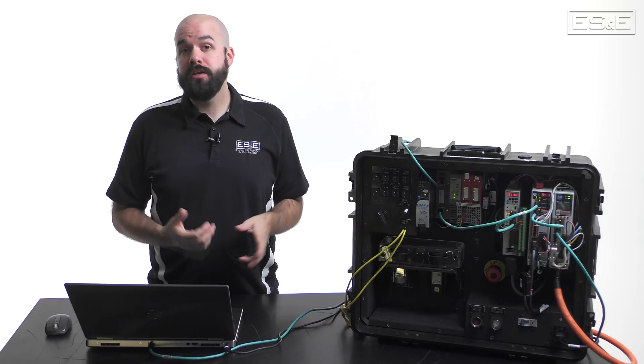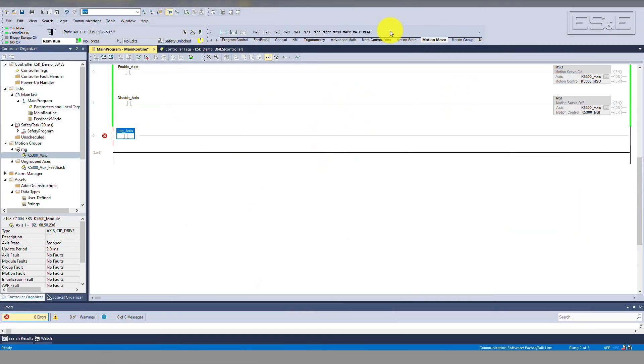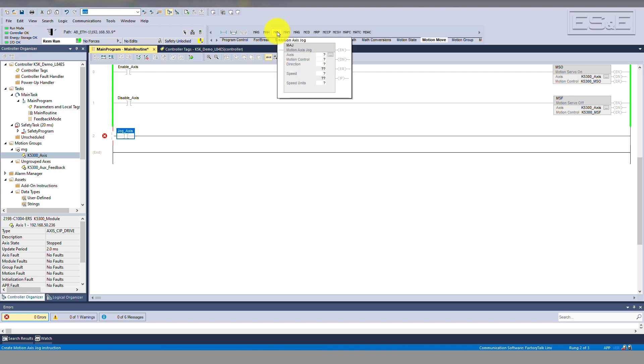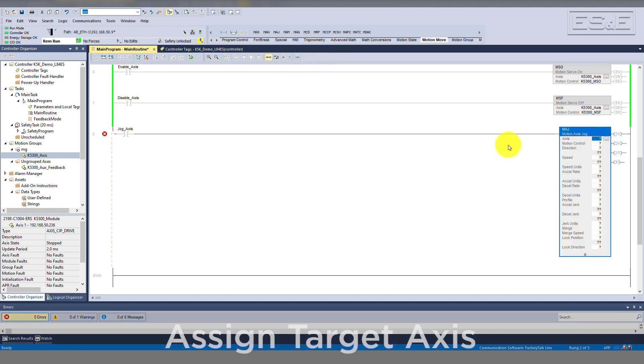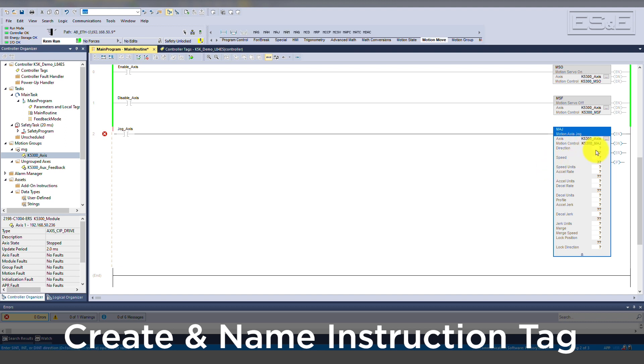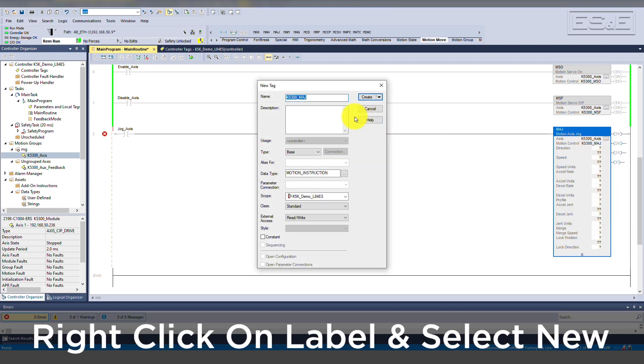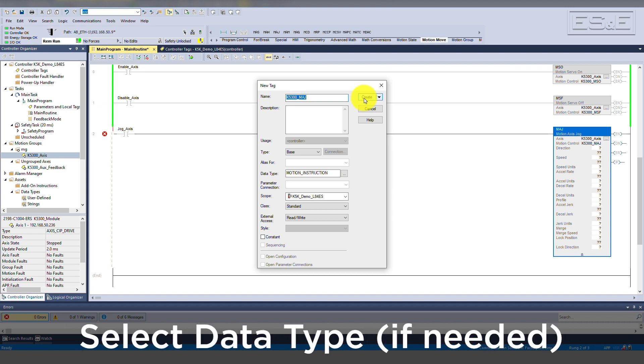Now let's build the instruction in ladder logic. You can find the MAJ instruction under the Motion Move tab of the ladder logic instruction selector. Assign the target axis, then create an instruction tag. It's a good idea to name the instruction tag after the instruction itself — that way when troubleshooting in the future it will be easier to find the tag. Right-click on the label and select New to create the tag in the tag database. The tag will be of type Motion Instruction. Select Create.